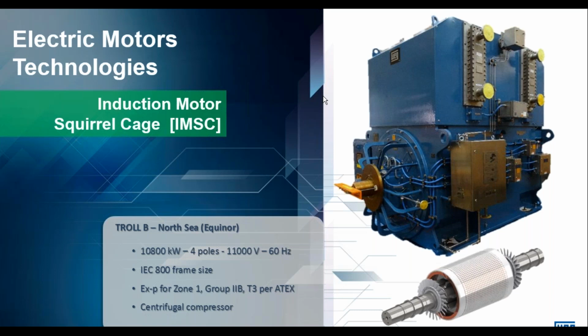Okay, so we're going to take a look at some of the typical motor designs. The first and most common one, and by far the simplest in terms of construction, would be the squirrel cage induction motor. The fact that it is the simplest to manufacture gives us some specific advantages. It is inherently robust. It is reliable. From a CapEx and OpEx point of view, it is comparatively the lowest of all the motor types to install. It undoubtedly has the smallest footprint, a pretty good efficiency, and it can easily be used with other starting methods, for example, VSD or other types of indirect starting method.